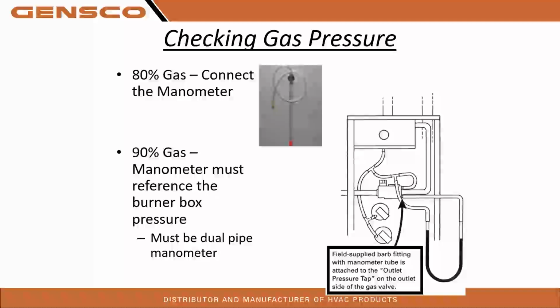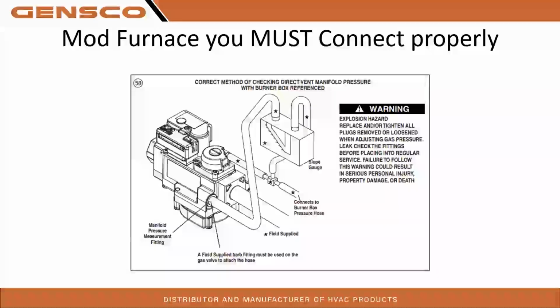So when you get into the mod furnaces and stuff like that, you have to do this correctly. Otherwise, you're never going to get your stuff set up correctly. And then you'll get PS1 issues over and over again because that mod furnace doesn't understand, because you didn't reference it properly. So when you did your gas valve minimum maximum setup and you didn't reference the burner, it's not going to be right. It'll never be right. So if you have a mod furnace out there with PS1 issues, I would highly recommend you connect to it properly and do that test, gas valve minimum, gas valve maximum setup, so it knows what the low and the actual high is.